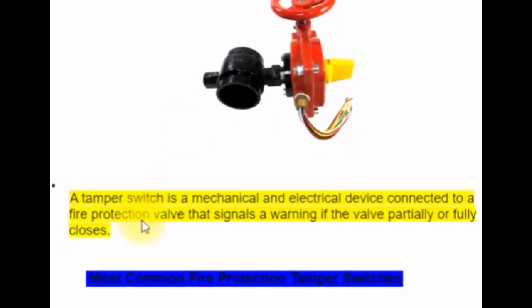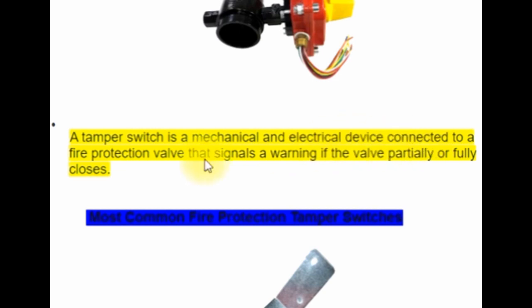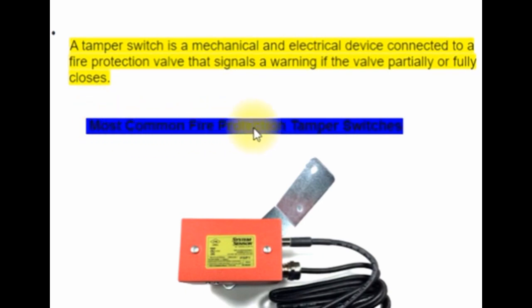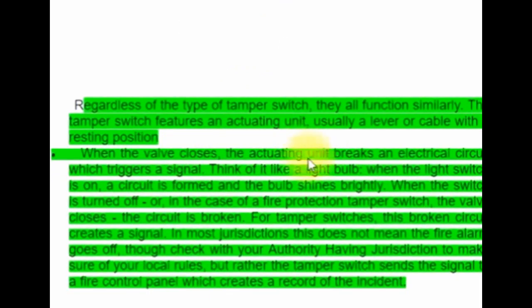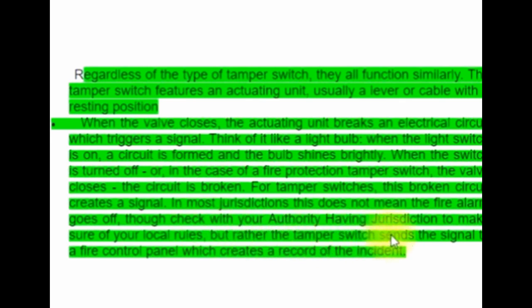A tamper switch is a mechanical and electrical device connected to a fire protection valve that signals a warning if the valve partially or fully closes. Most common fire protection tamper switches function similarly. The tamper switch features an actuating unit, usually a lever or cable, with a resting position. When the valve closes, the actuating unit breaks an electrical circuit which triggers a signal. Think of it like a light bulb - when the light switch is on, a circuit is formed and the bulb shines brightly. When the switch is turned off, or in the case of a fire protection tamper switch the valve closes, the circuit is broken. For tamper switches, this broken circuit creates a signal. In most jurisdictions, this does not mean the fire alarm goes off. Check with your authority having jurisdiction to make sure of your local rules. Rather, the tamper switch sends the signal to a fire control panel which creates a record of the incident.